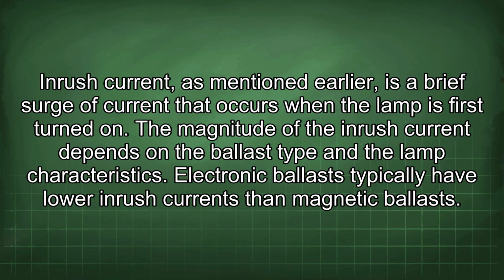Inrush current, as mentioned earlier, is a brief surge of current that occurs when the lamp is first turned on. The magnitude of the inrush current depends on the ballast type and the lamp characteristics. Electronic ballasts typically have lower inrush currents than magnetic ballasts.